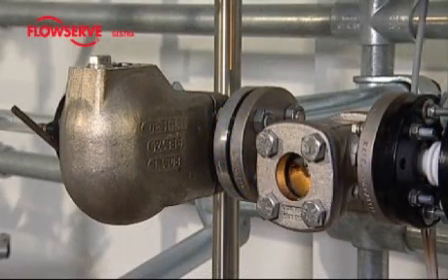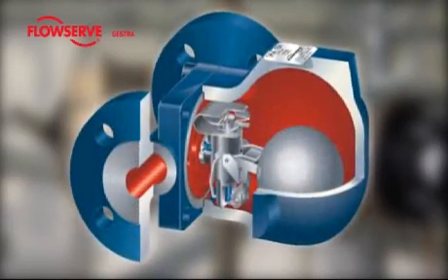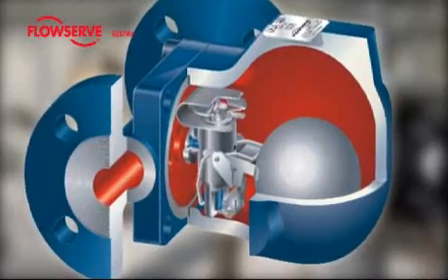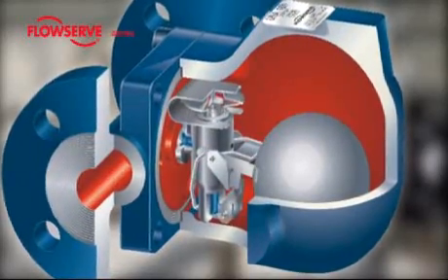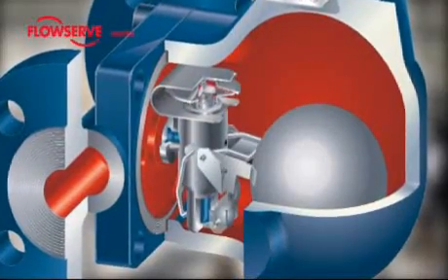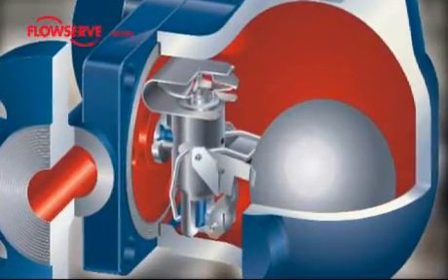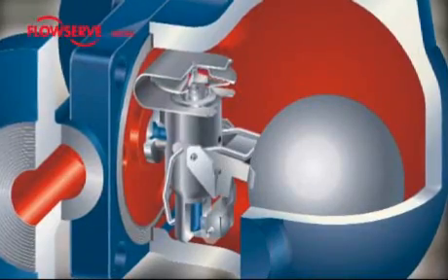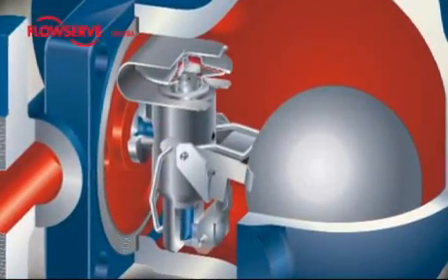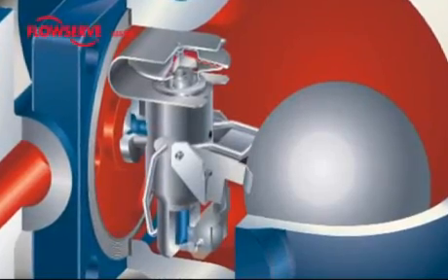GESTRA ball float traps have a regulator which functions by having a float roll a ball off an orifice when condensate flows into the body. This opening is called the orifice, and can have various diameters depending on the differential pressure. Through the differential pressure that is applied, the condensate is pressed through this small orifice and flows through the condensate line into the vessel located downstream.